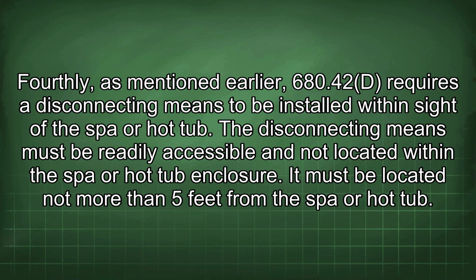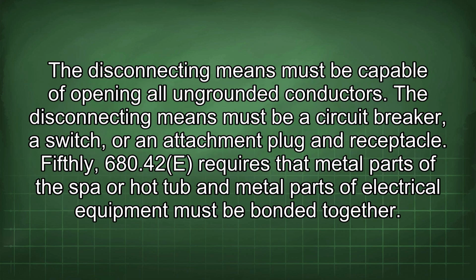Fourthly, as mentioned earlier, 680.42(D) requires a disconnecting means to be installed within sight of the spa or hot tub. The disconnecting means must be readily accessible and not located within the spa or hot tub enclosure. It must be located not more than 5 feet from the spa or hot tub. The disconnecting means must be capable of opening all ungrounded conductors. The disconnecting means must be a circuit breaker, a switch, or an attachment plug and receptacle.